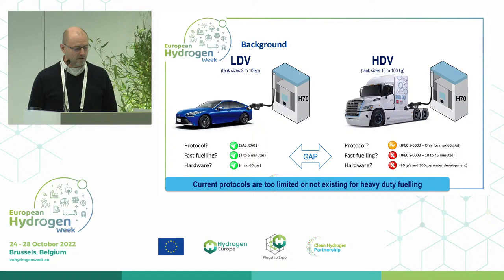There was also within this protocol a possibility to fuel heavy-duty vehicles, but there is quite a big gap. The SAE J2601 D-tables, or D category, came from the Japanese standard but used the same nozzle as for passenger cars — a maximum of 60 grams per second. So it was quite limited, and if you wanted to fuel large quantities, it would take a really long time: 30 to 45 minutes. There was a need for not only a new protocol, but also new hardware, to fuel faster and compete with diesel vehicles.